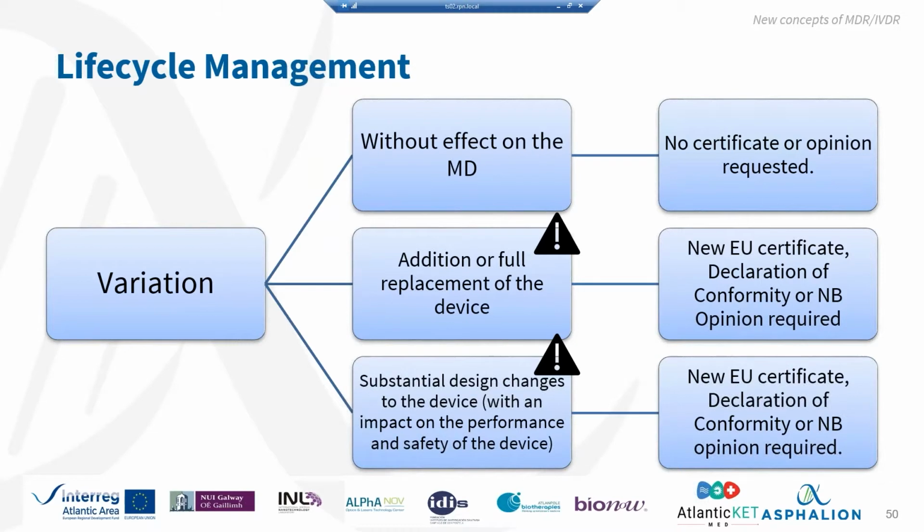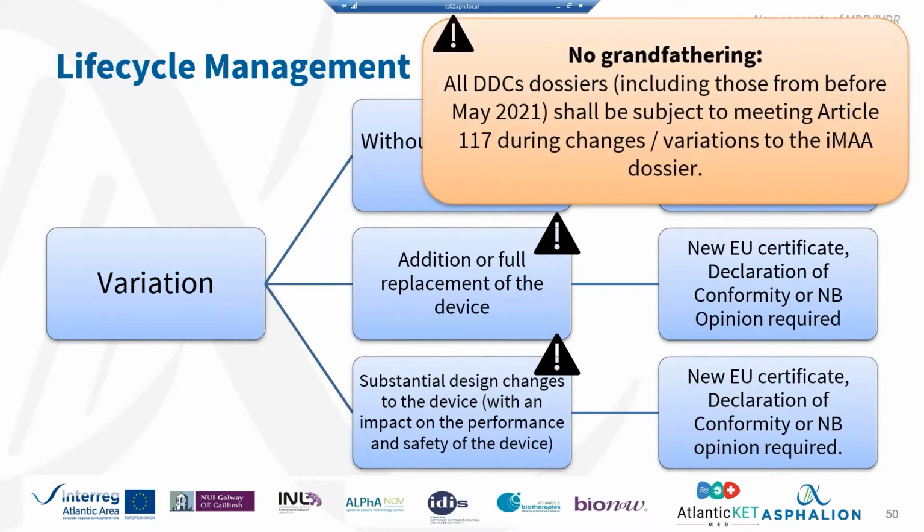Okay. It's important to clarify that there's no grandfathering. All the drug-device combination dossiers, including those from before May 2021, shall be subject to meeting this article. Which means that if you're now including a new device after May 2021, or a new format of device, you will have to provide a notified body opinion or a certificate, even though your product was authorized way before 2021.